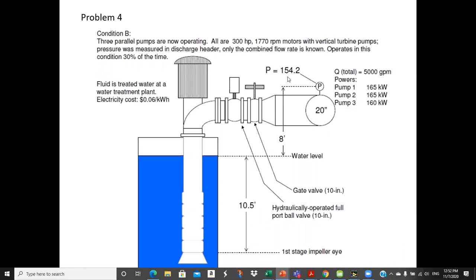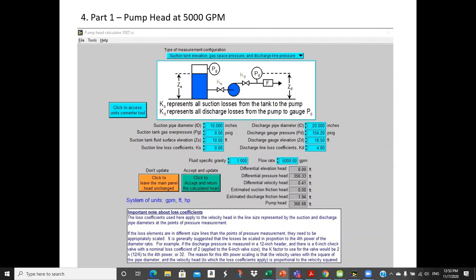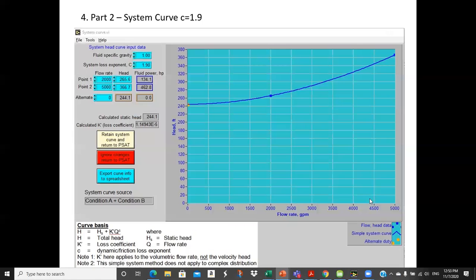Okay, and the power goes to 154.2 kW. I'm sorry, the pressure and the power. We had 170 before with 1 pump. With these 3 in operation, we have 165, 165, and 160. So we'll have to sum that, so we'll run one big equivalent pump in PSAT. Okay, so this is the head calculation at that point. I think the only thing that's really changed here is the discharge pressure and the flow. And so we're about 366.7 feet, something like that.